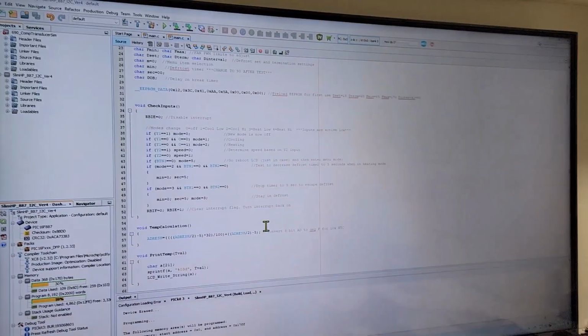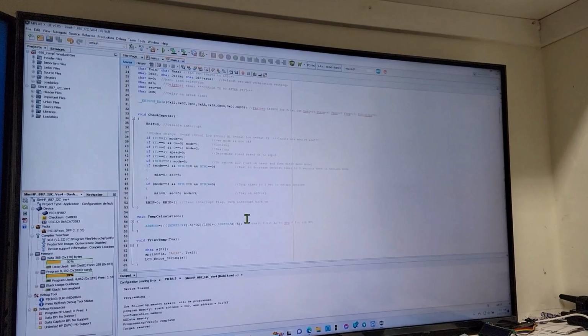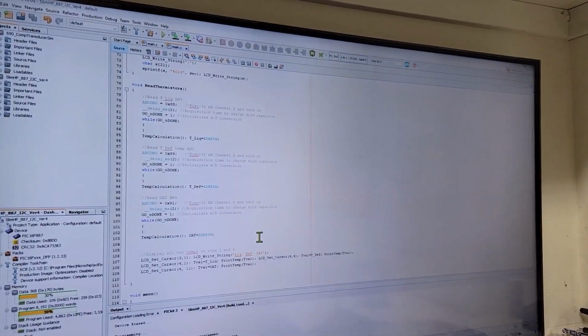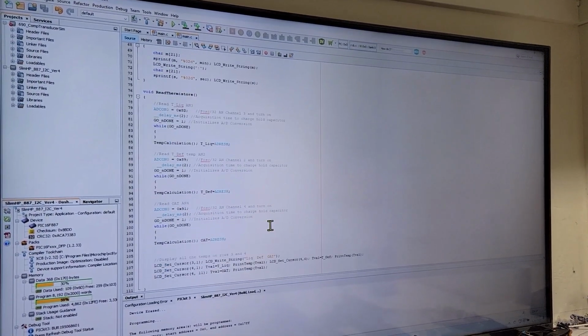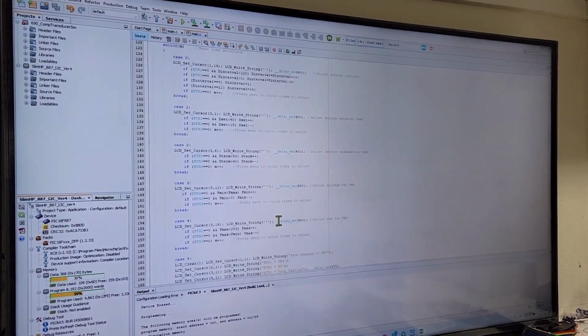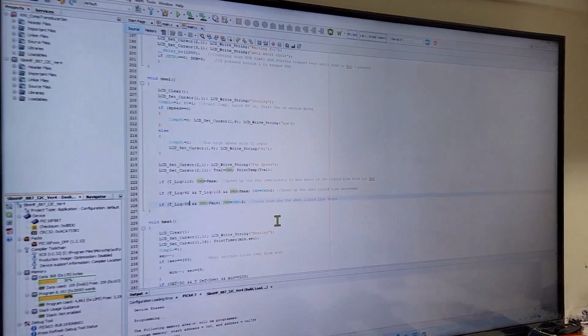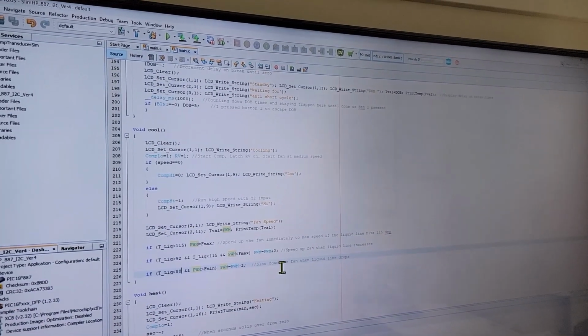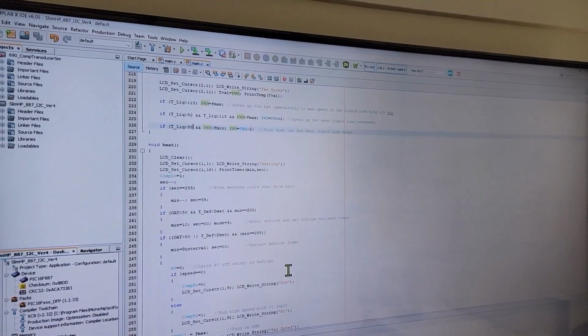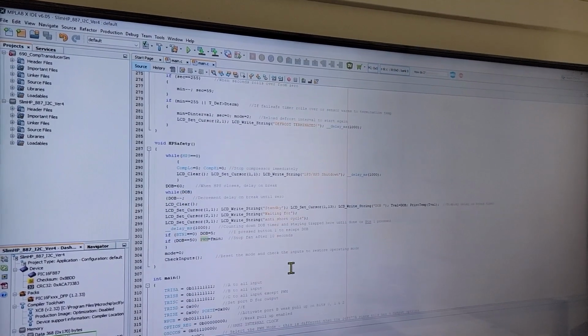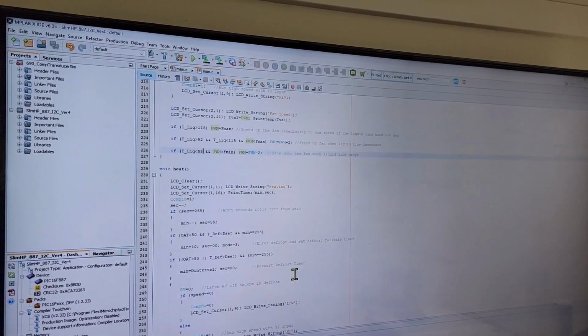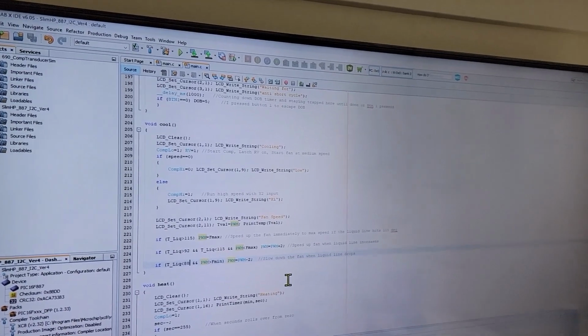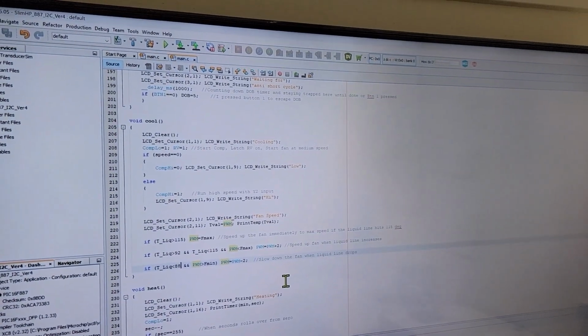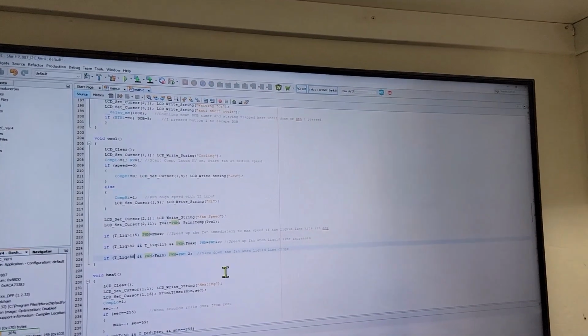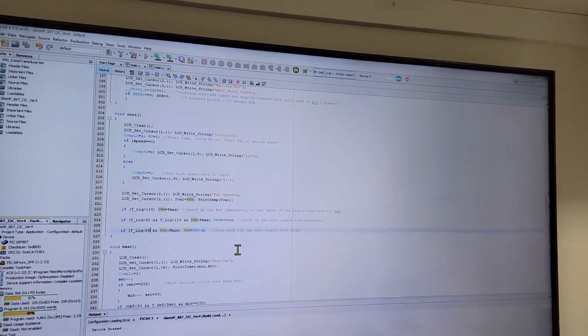Basically what's happening is it's running all these things. It could be reading my thermistors, which happens every second or so. It could be running my menus if I go into the menu, or say we're in the cool function, or heat, defrost, compressor safety, all that stuff. It could be in the middle of the cool routine, trying to go through this about every second, but 60 times a second it's being interrupted to go check inputs.